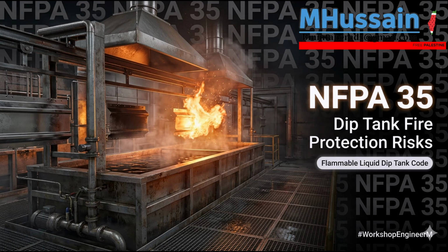That is a phenomenal piece of engineering. It's a brilliant way to save energy, but those electronic safety interlocks must be absolutely bulletproof. Yeah, they have to be. And speaking of explosions, we have to talk about deflagration venting. If a building handles Class IA liquids or processes materials above their boiling points or has combustible dusts, the standard says a deflagration hazard exists.